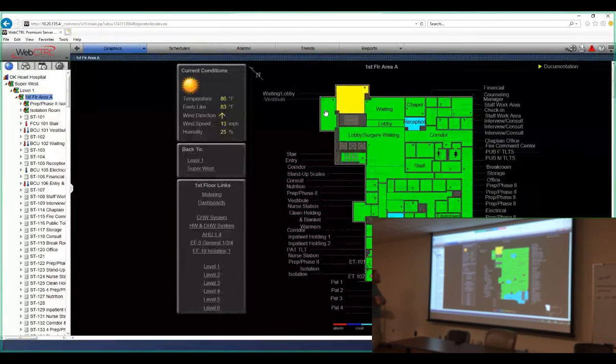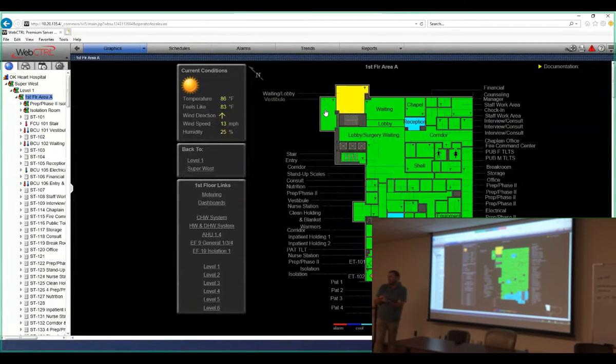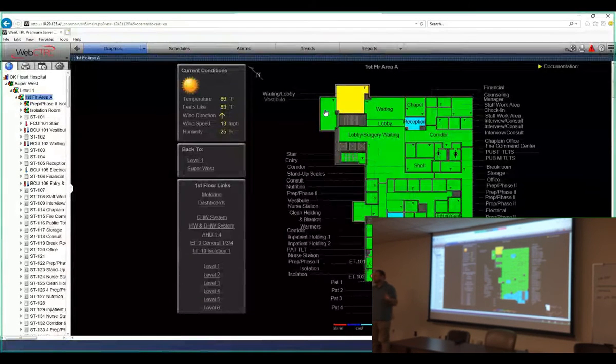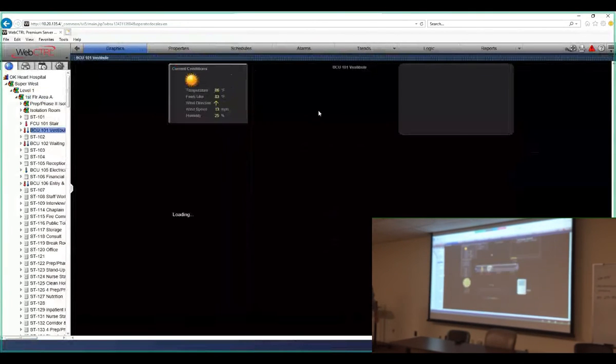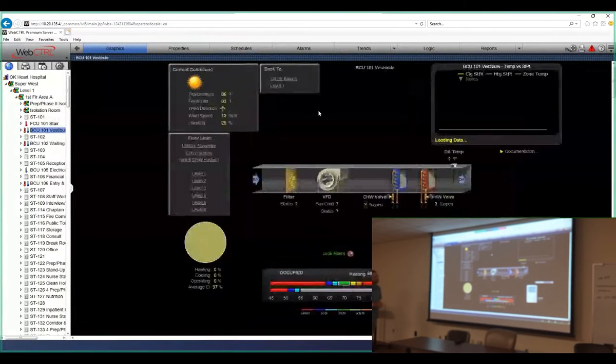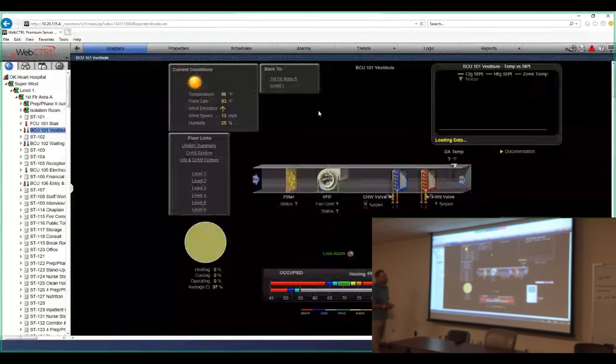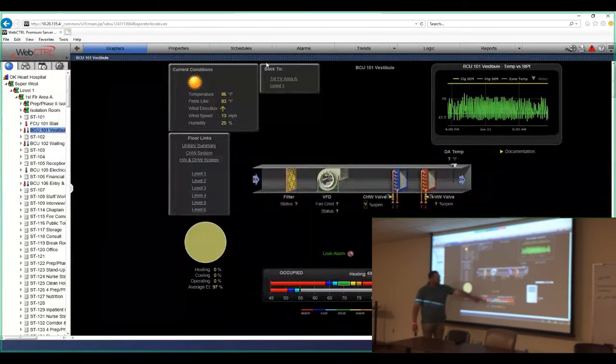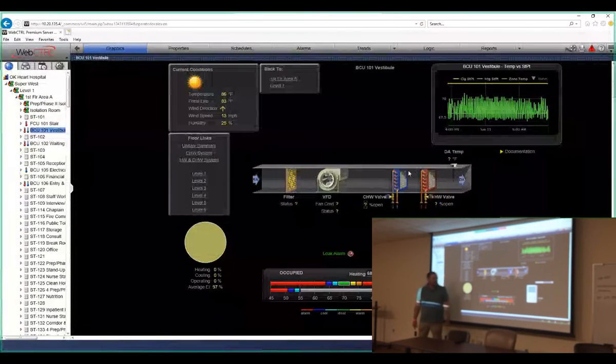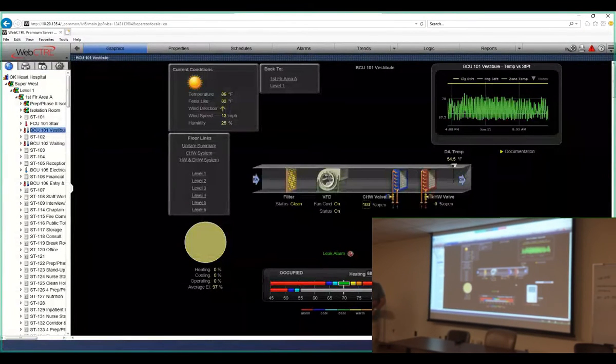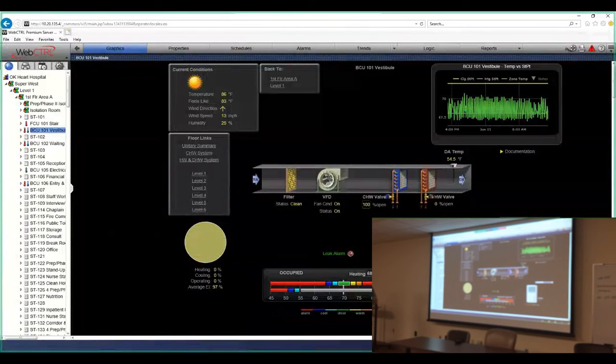So a lot of the blower coil units, you may have ones that are cooling only. I don't think we have any that are heating only, but most of them can be cooling only or cooling and heating, like this vestibule unit Joe clicks on here. You pull up the graphic, just like all the other equipment, and pull up the set points. Right now it's currently set at 72 to 68: 72 is our cooling set point, 68 is our heating set point.